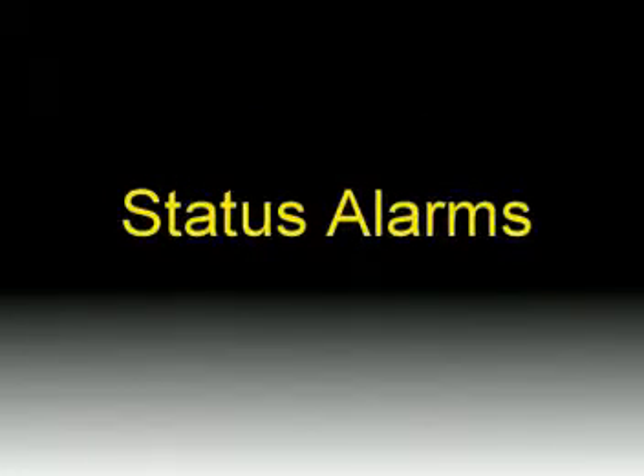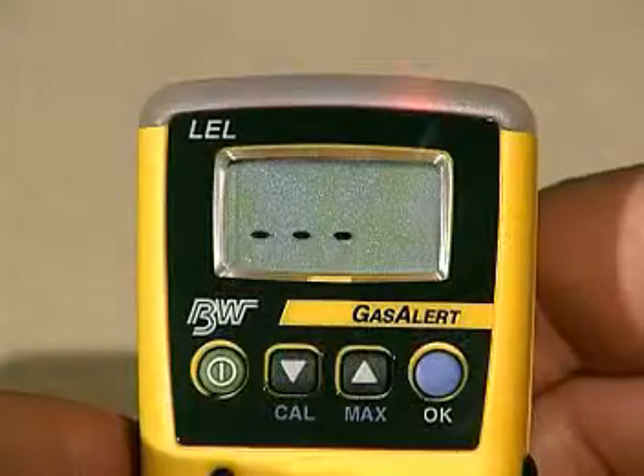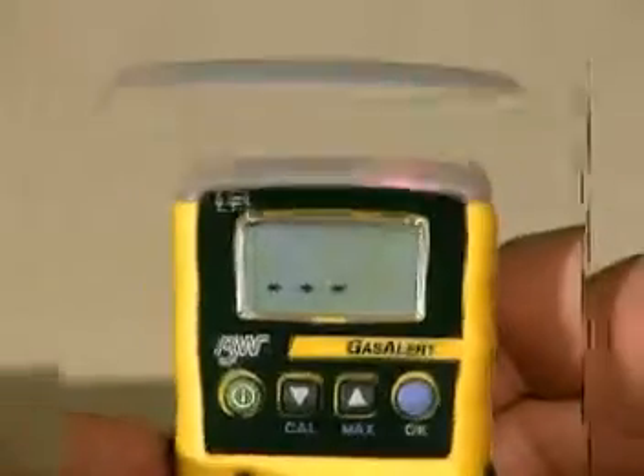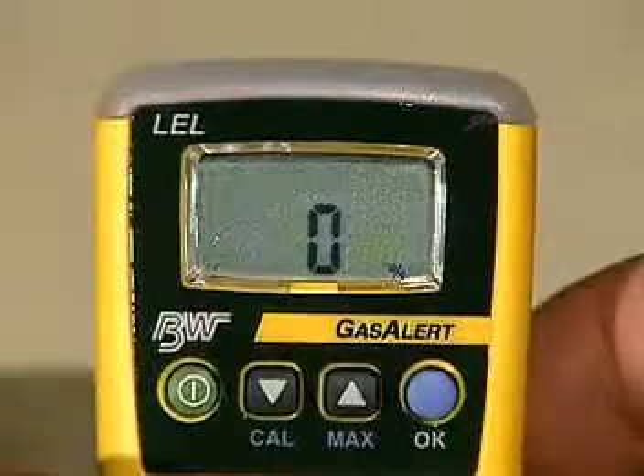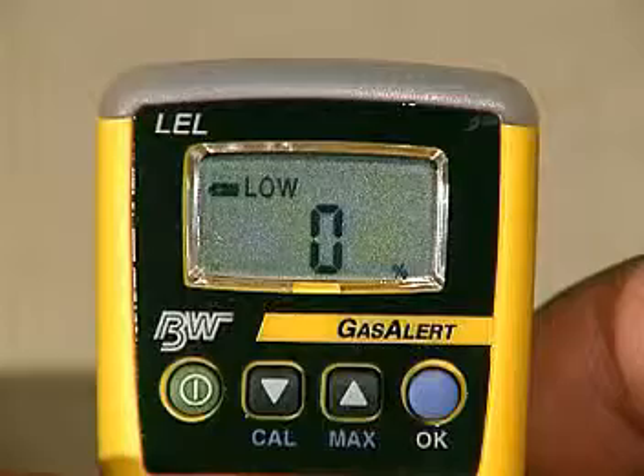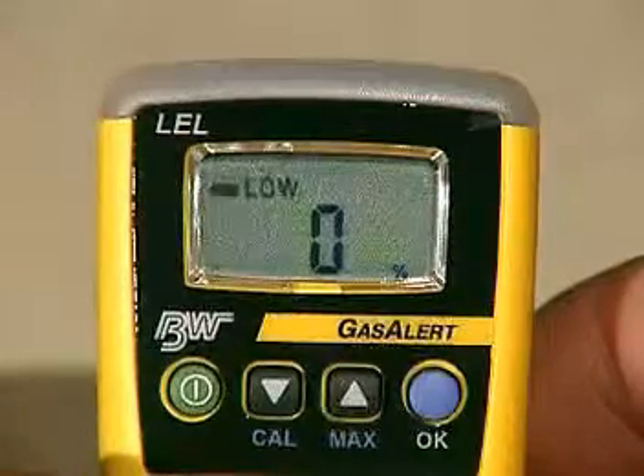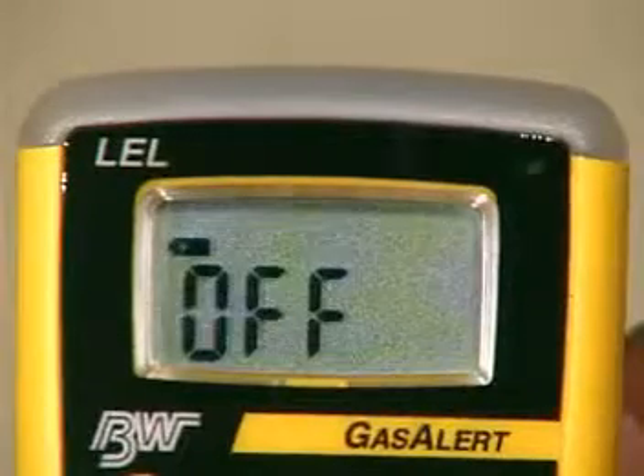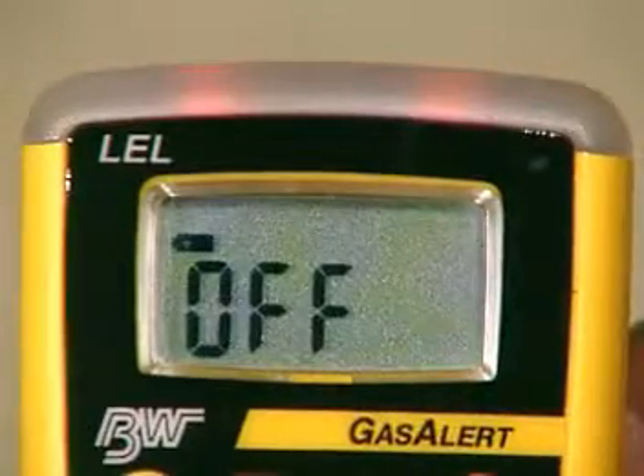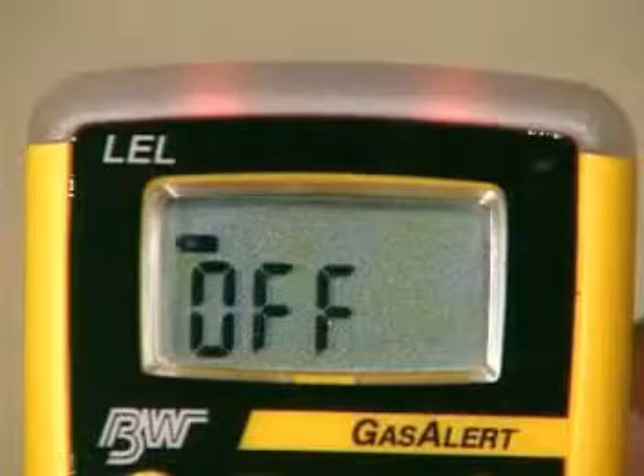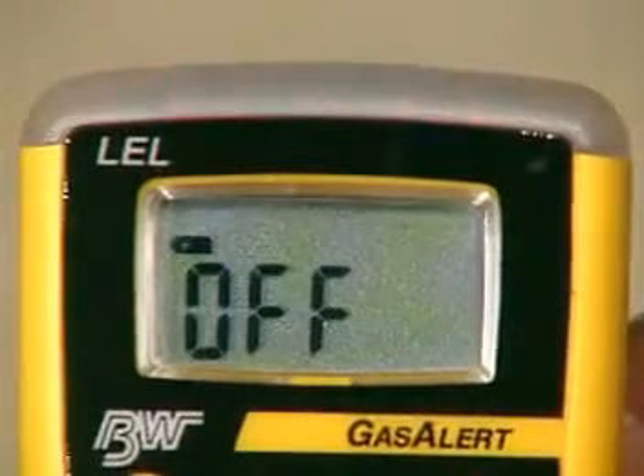GasAlert-LEL constantly analyzes and tests its own operational status. The sensor alarm activates if the sensor is missing or defective. The low battery alarm is activated if power drops below usable levels. The alarms pulse once every 5 seconds. To prevent unsafe usage, the automatic shutdown activates if the battery power is in immediate danger of dropping below the minimum operating voltage.